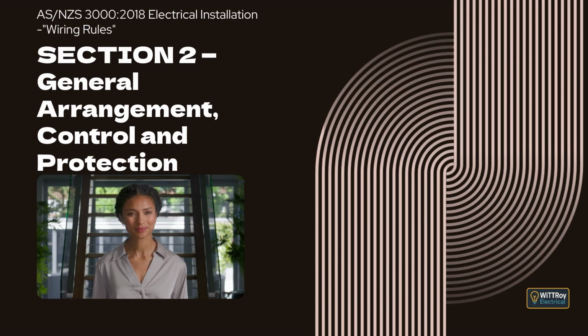Clause 2.9. Protection against fire hazard due to arcing faults. Clause 2.9.1 General. In this part of AS/NZS 3000, we talk about arcing faults and the fire risk they create. An arcing fault is when electricity jumps across a damaged or loose connection. It creates heat, sparks, and can easily start a fire inside a wall, a socket, or a cable. Arc fault detection devices, spoken as AFDDs, are designed to detect this kind of fault early and disconnect the supply before a fire can start.